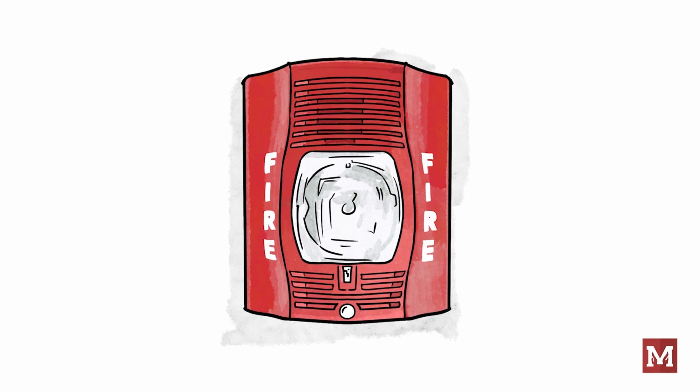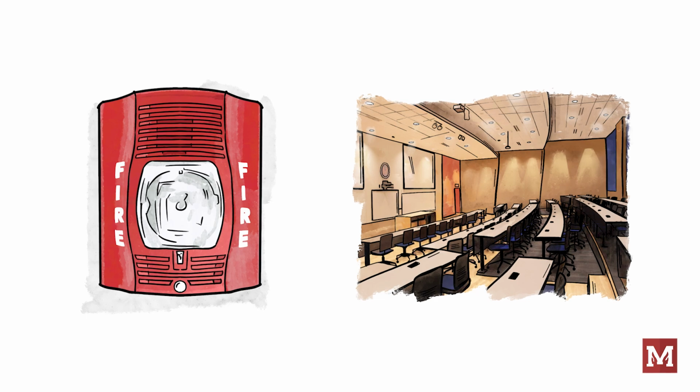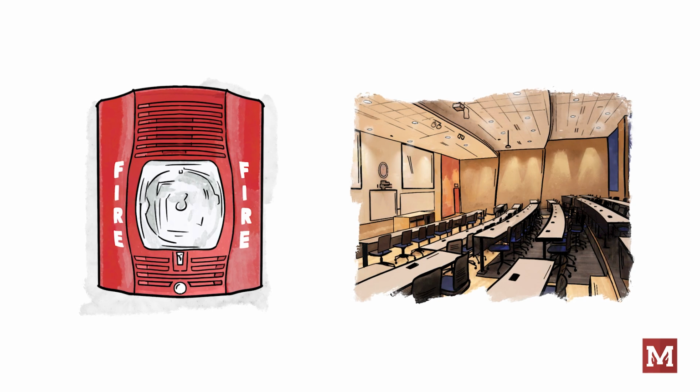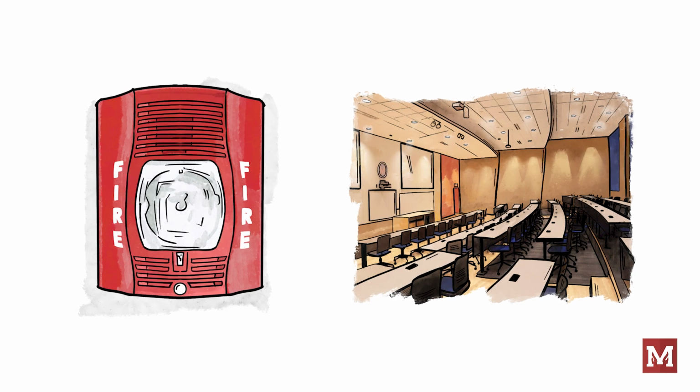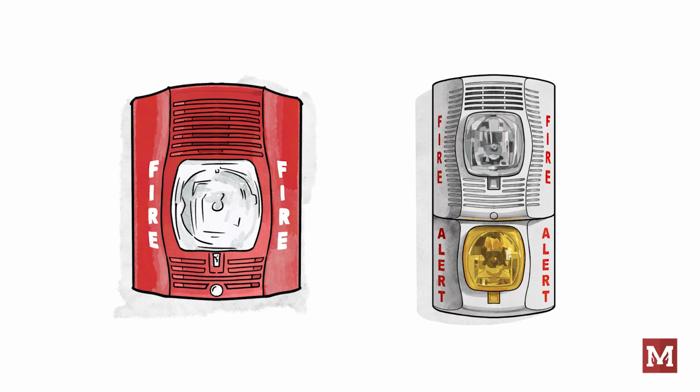Now, we don't necessarily have to cover every single surface within a room, especially when we think about environments that have a lot of furniture or obstructions, but we need enough light, whether indirect or direct, that can make it obvious to someone in the space that an emergency condition is happening. White light through a clear lens is the baseline for most fire alarm systems. We can tint the lens, though, so a colored amber or yellow light may be used in combination with other emergency systems. The clear lens is the most commonly used setup today.